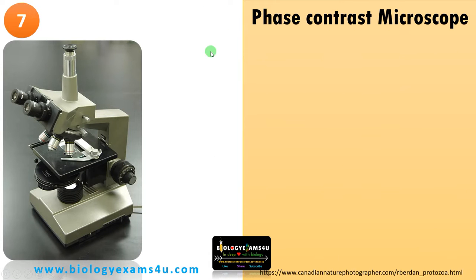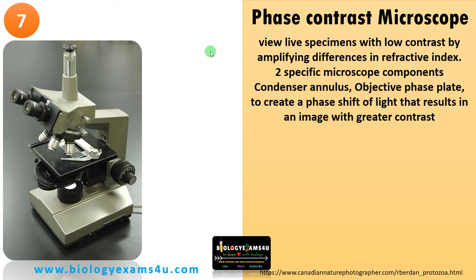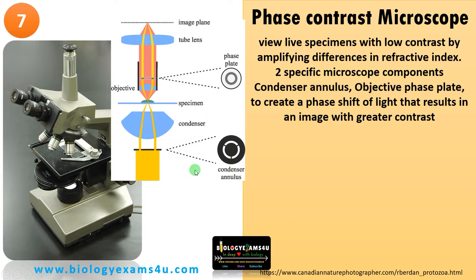Seventh in the list is the phase contrast microscope. It is used to see live specimens with low contrast by amplifying differences in refractive index. There are two specific components: the condenser annulus and the phase plate. The condenser annulus creates a hollow cone of light, and the phase plate converts the phase shift into an intensity shift detected by the objective, enhancing contrast.